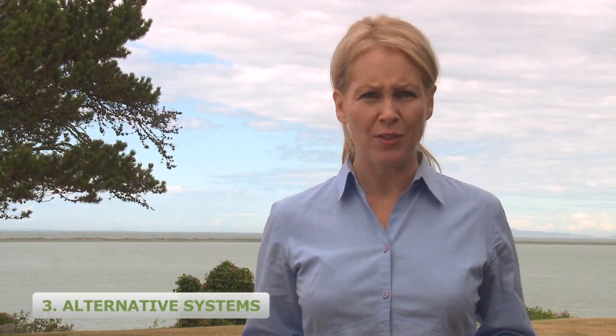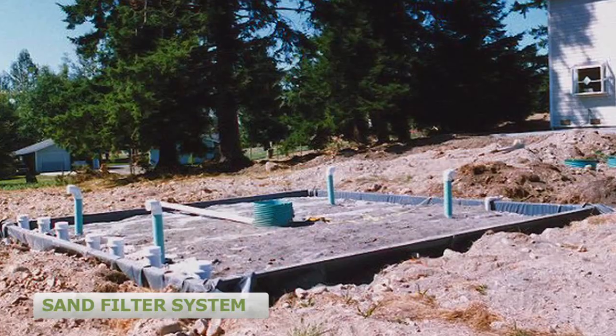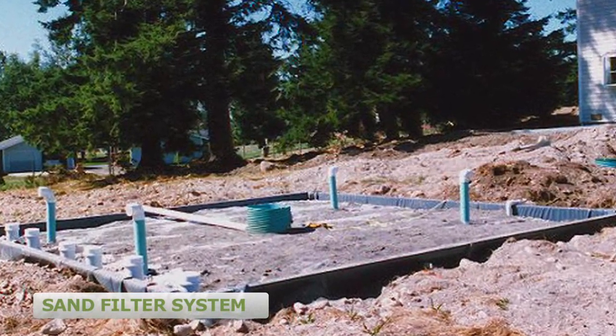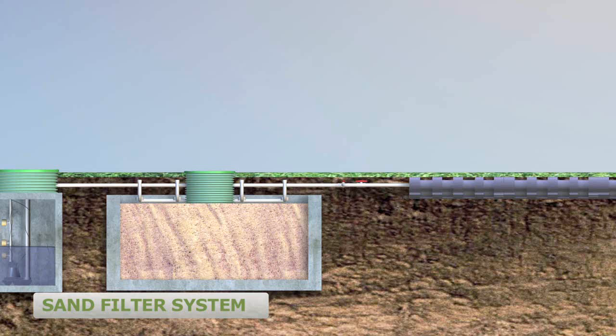Another type of alternative system is the sand filter system. A sand filter is basically a box of engineered sand and gravel which treats the wastewater. A sand filter requires only one and a half to two and a half feet of suitable native soil. The wastewater is applied at the top of the sand filter and flows down through the sand and gravel receiving treatment. Then the pre-treated wastewater flows either by pressure or gravity to a drain field for final treatment and dispersal.